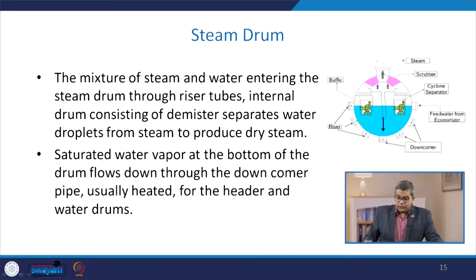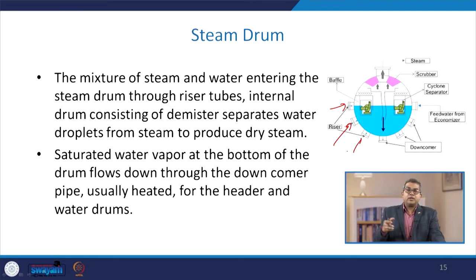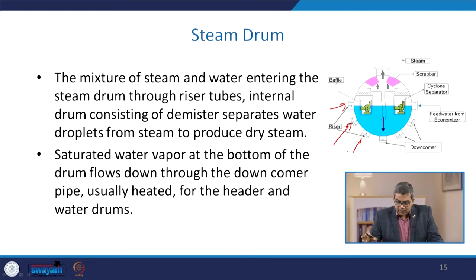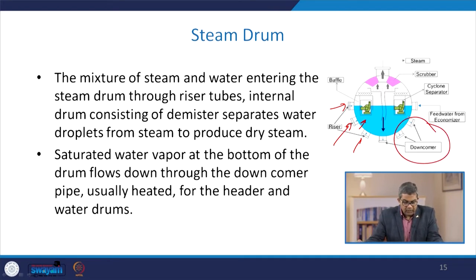The integral parts of steam drums include: the mixture of steam and water entering the steam drum through the riser tubes; an internal drum consisting of a demister, which separates water droplets from the steam to produce dry steam; and saturated water vapours at the bottom of the drum flowing down through the downcomer, which is usually connected to the header and water drums.